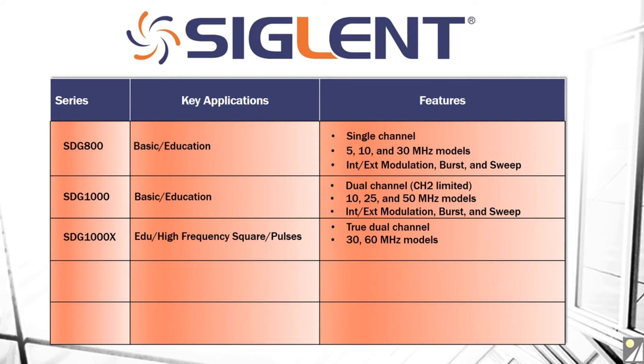Now let's move to the SDG1000X series, which is one of our newer platforms. This is more of a high frequency square or pulse wave application focus, and it is a true dual channel instrument, so both channels are identical as far as their output and function capabilities. We have 30 and 60 MHz models. Where this instrument stands out is that the square max frequency is identical to the sine max frequency. So in the 30 MHz model, you have 30 MHz sine wave maximum and 30 MHz square wave maximum, which is helpful if you are going to be doing pulsing or high frequency square waves.